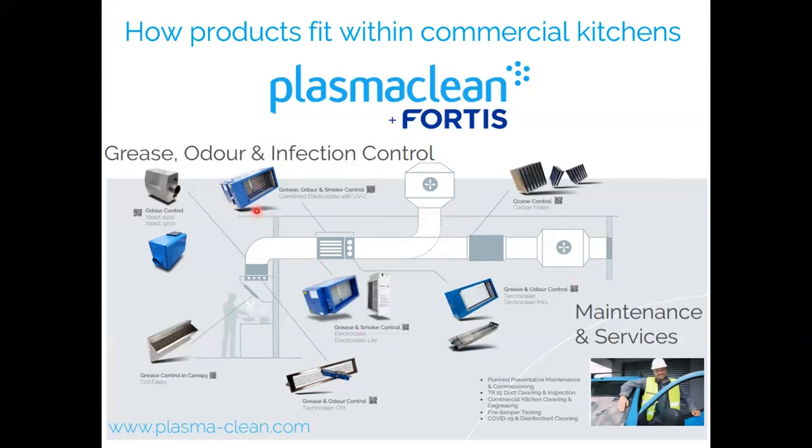Now you can see there's a combined electrostatic with UVC system. Essentially, this particular system itself is a one-stop shop for grease, odour and smoke control, especially when it's combined with UVC, as you can see there. So this is an ESP on its own for grease and smoke control, and then the ESP UV there is for grease, smoke and odour control. They're around 95% effective in removing grease, smoke and odour, and can be increased in terms of efficiency with single, double and triple pass arrangements.